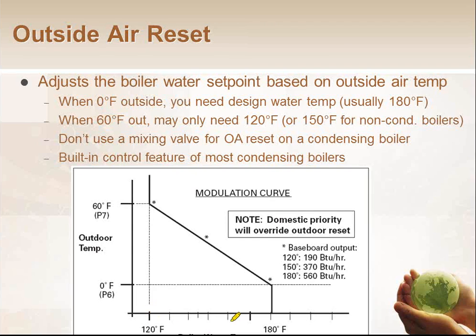So this chart here is a typical outside air reset schedule. This particular one goes from 120 to 180-degree supply water, and it goes from 0 to 60-degree outdoor air temperature, right? So if it's 0 degrees outside, or anything colder than 0 even, give me 180-degree water. If it's 60 degrees or higher outside, give me 120-degree supply water. And then I can pick anything in between. If it's 30 degrees outside today, give me 150. If it's 10 degrees outside, give me, I don't know, 168 or whatever the number comes out to be.